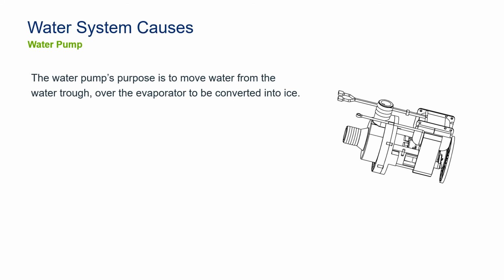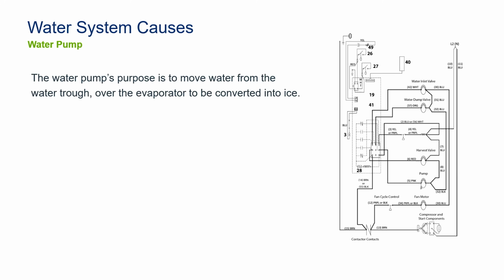What about the water pump? So the water pump's job is to move water from the water trough over the evaporator and convert it into ice. If that water pump is not running, we need to verify things like, do we have power to the water pump? Is the water pump flow path restricted? Those are the things you have to start looking at here. So how do we do that?